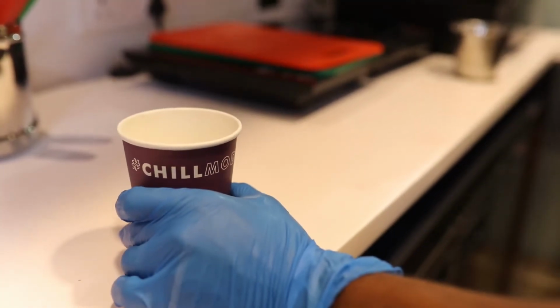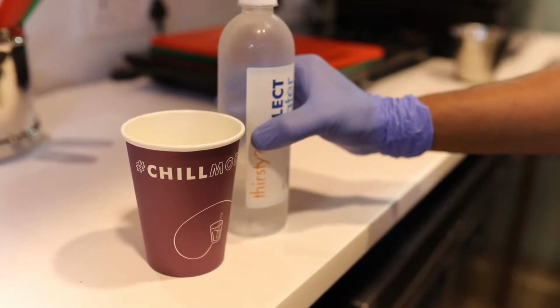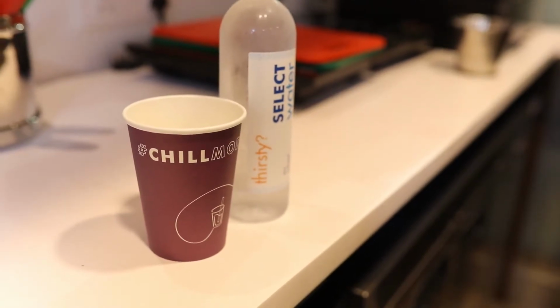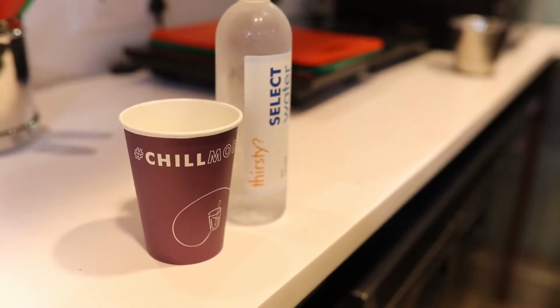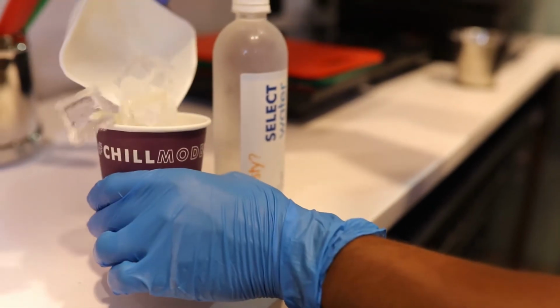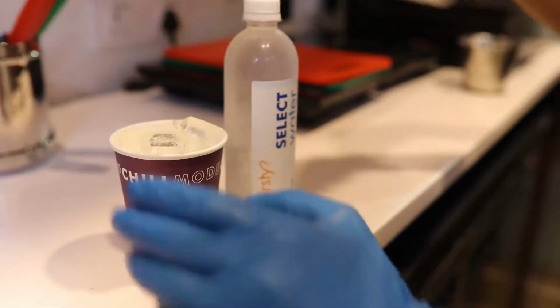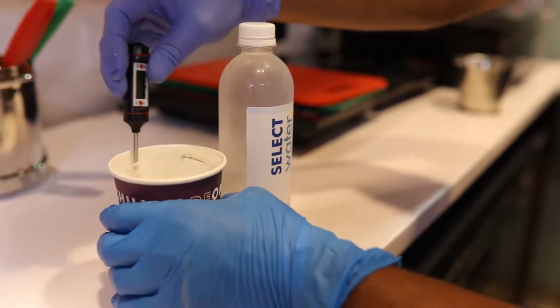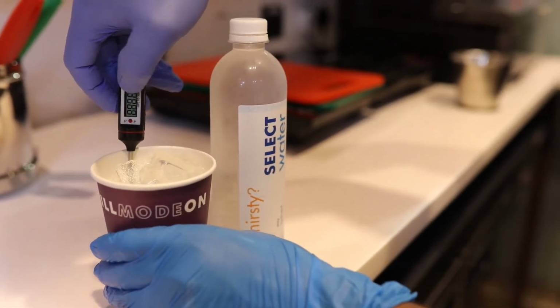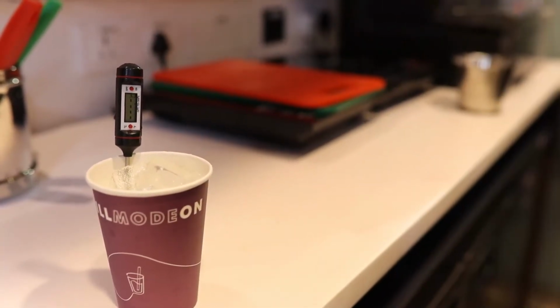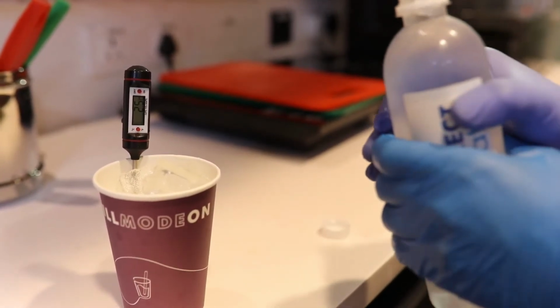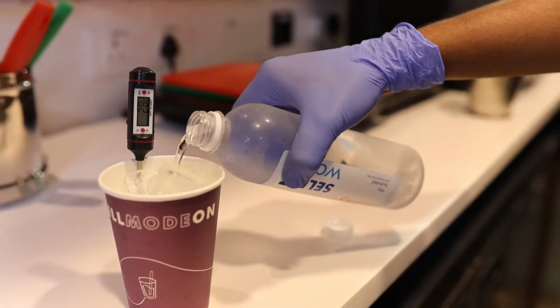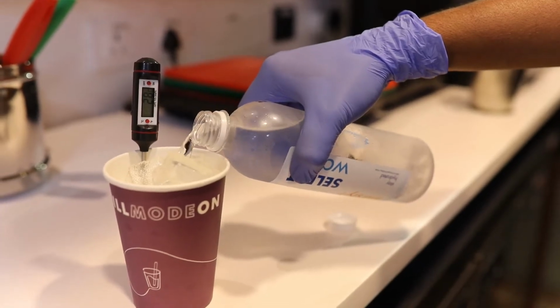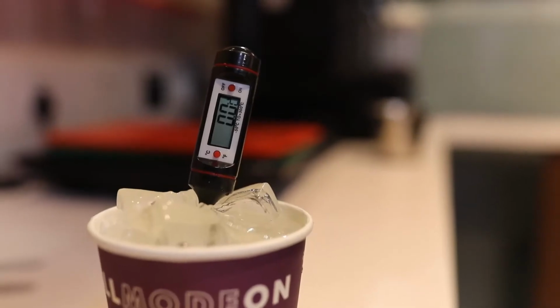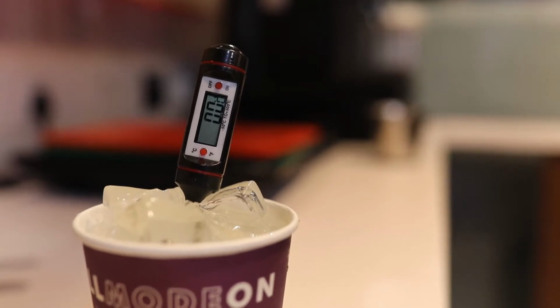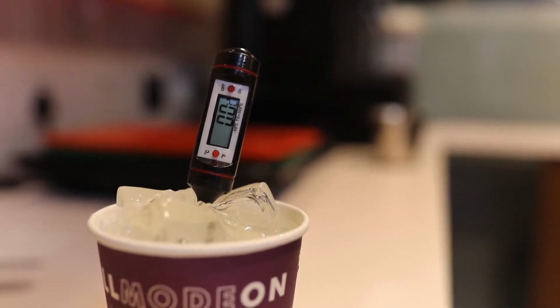Let us see how to perform an ice test to confirm that the probe is reading the right temperature. Take a glass and fill it with ice till the top, insert the probe, add cold water into the glass and wait for the temperature reading. If the temperature reading is 0 degrees centigrade, it means that the probe is reading the temperature correctly.